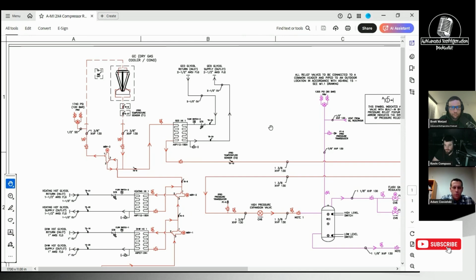It is like Güntner, they have something inside their control, depending on how many fans. If it's a large system, you have the possibility to turn down the fans and then turn them off. But a lot of people don't enable the LMCC control, and that will actually start cycling fans off when you get to 10% and/or below. And it makes a huge difference. And I've just been doing tests where I limit the RPM to 0.